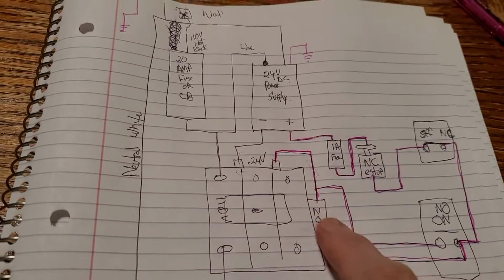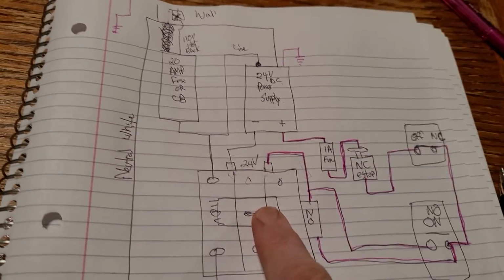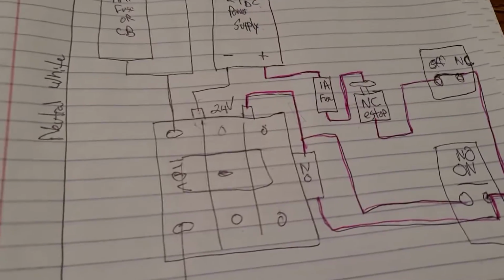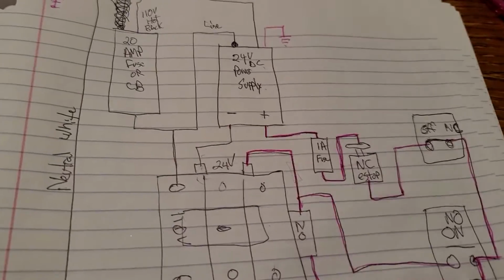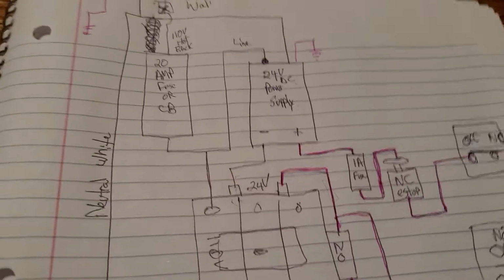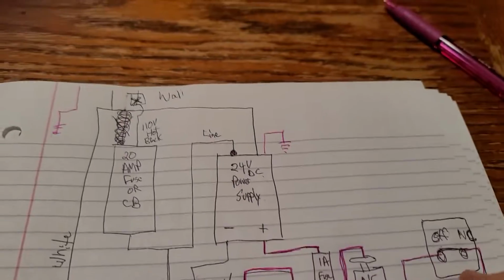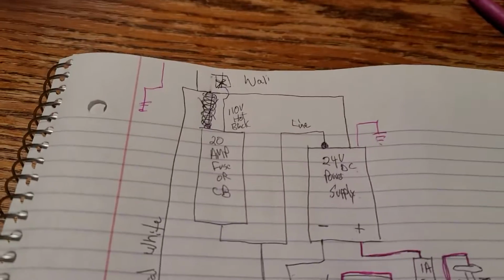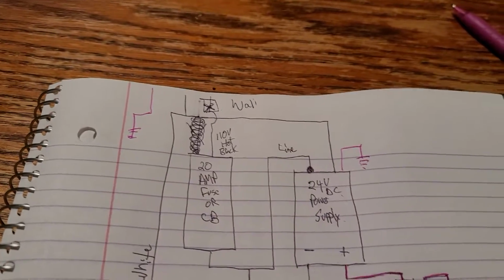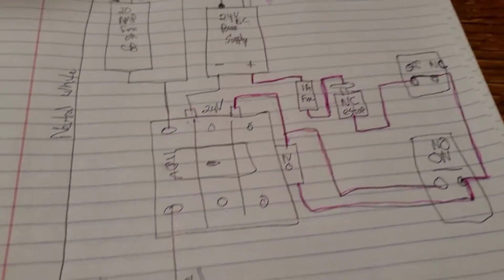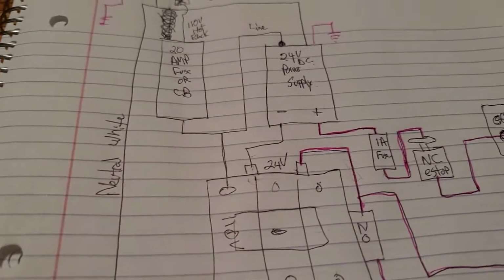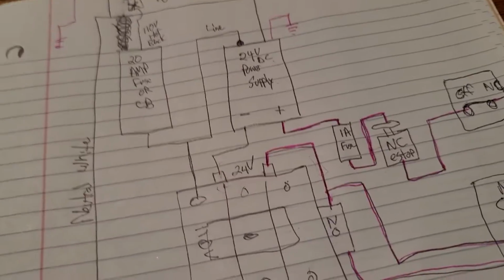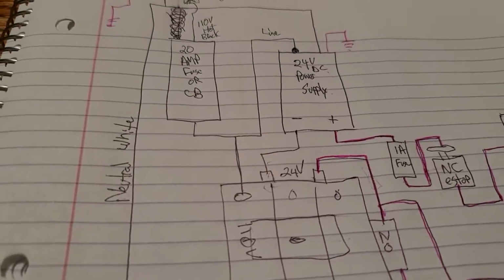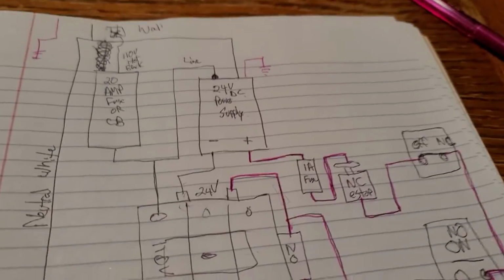Okay? That stays powered and will stay sucked in until we break the circuit. Okay? And the reason for that is power is now going all the way through and going through here up to the coil, and it stays latched, right? So that's now it's on. When that happens, 110 volts is going through the contactor and supplying all of your devices. Everything down here. So, how does it turn off?